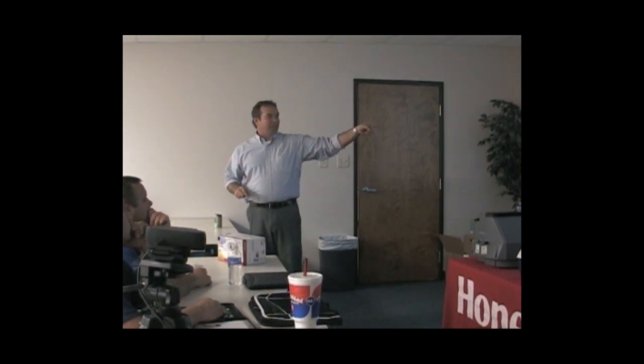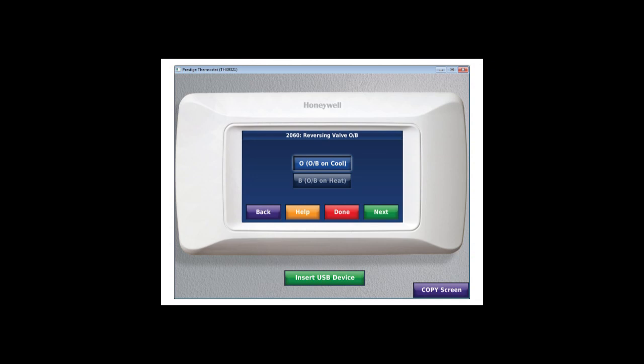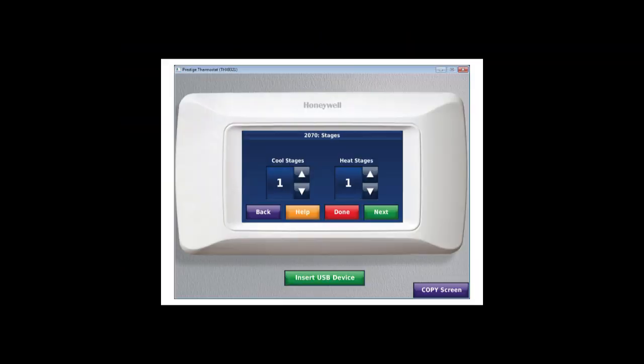So you're going to have to switch this to B, because you're the only one that's different. Everybody else is going to energize on cool. That's just your reversing valve action. It defaults to the majority. I changed my compressor stages. I got two compressors, 2 stages of backup heat.